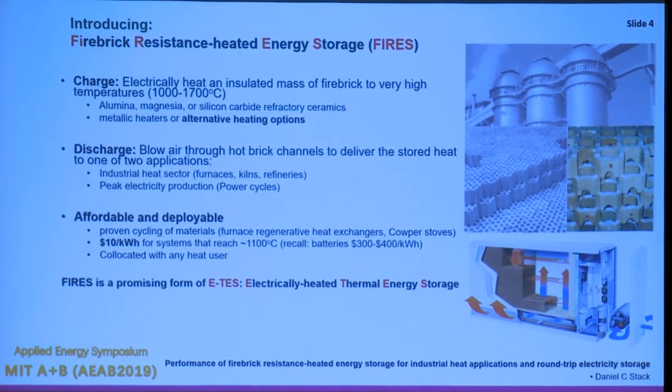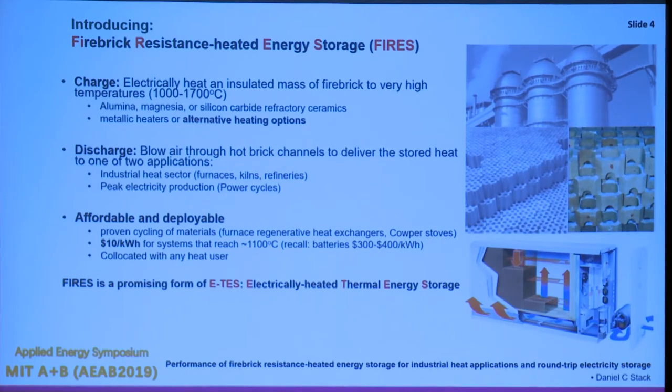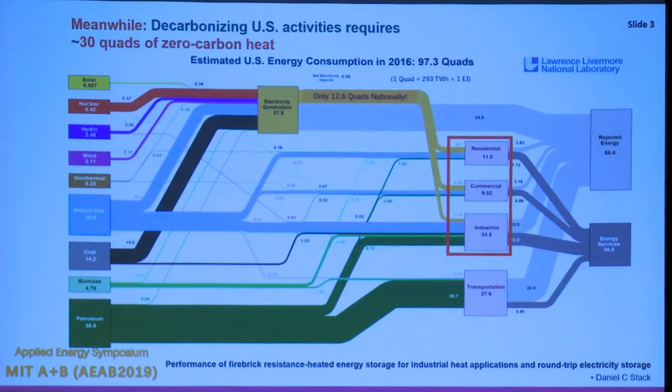It's affordable and deployable because brick is cheap and heaters are fairly cheap. You can find prices now for small systems that do this at around $15 per kilowatt hour — recall that batteries are much more expensive. We can co-locate with any heat user. I'm calling this E-TES: electrically heated thermal energy storage, a big field I think should be much more utilized as we deploy more renewable and nuclear energy.